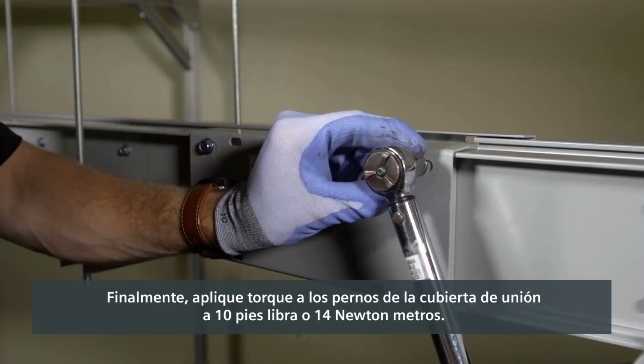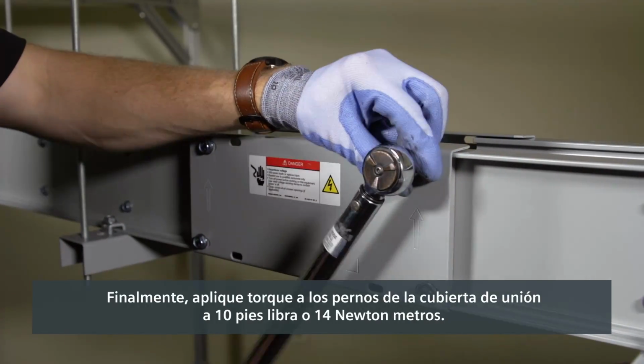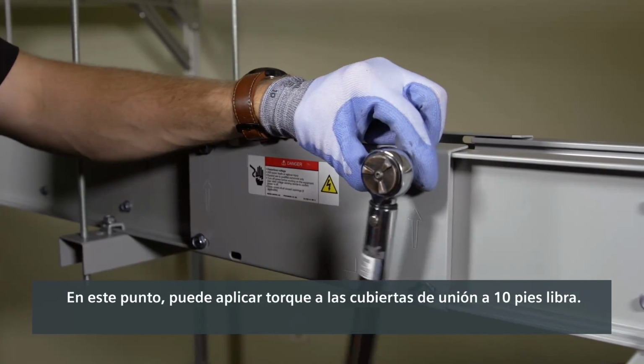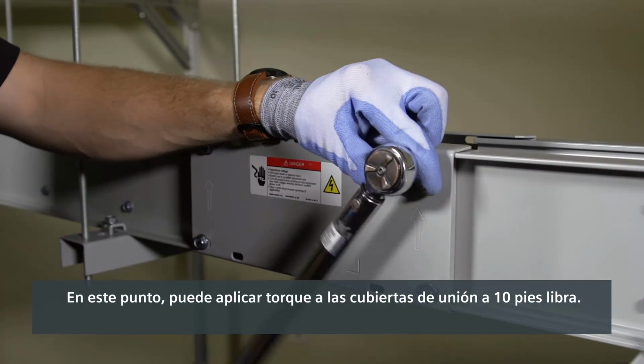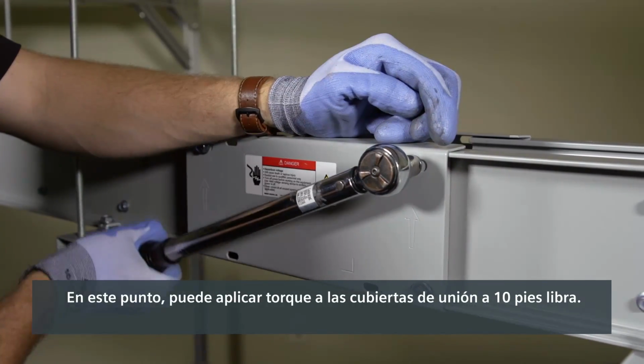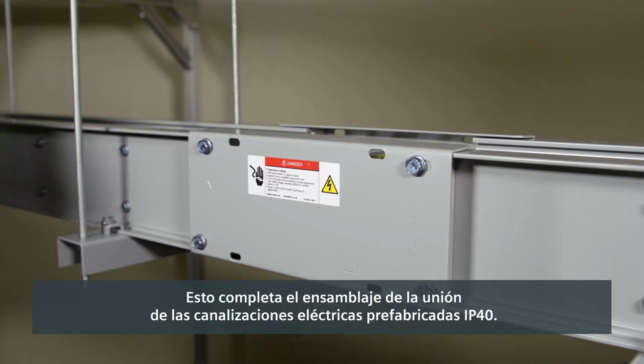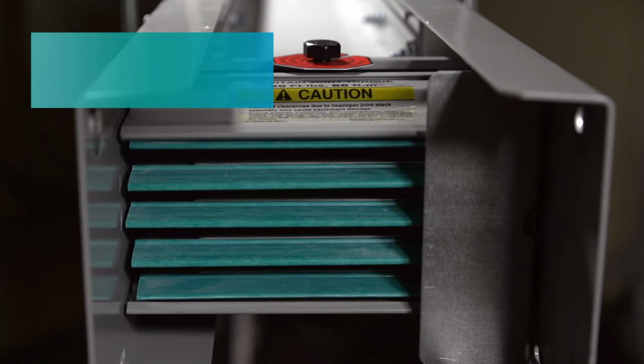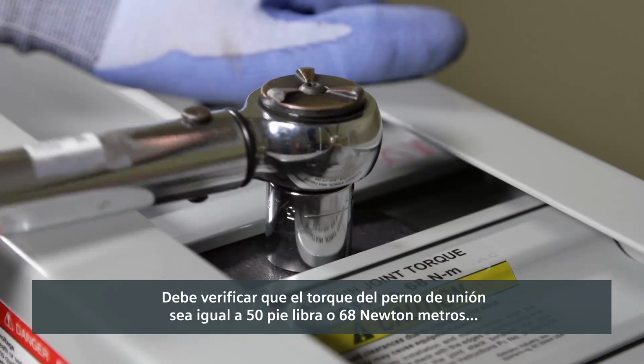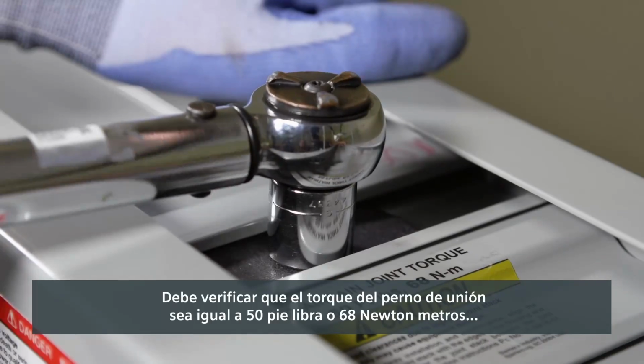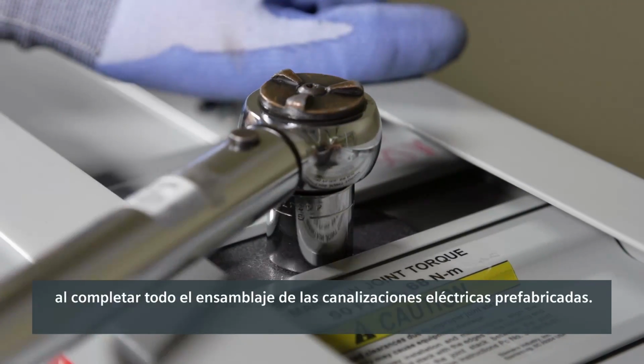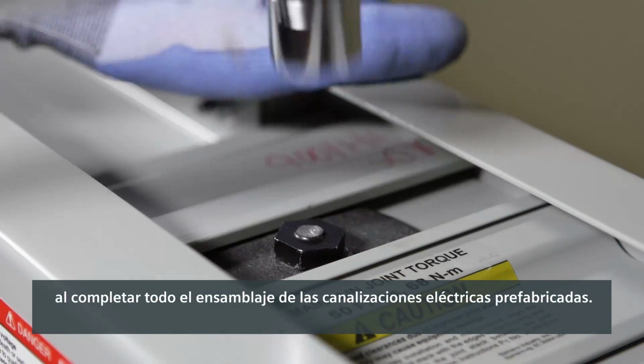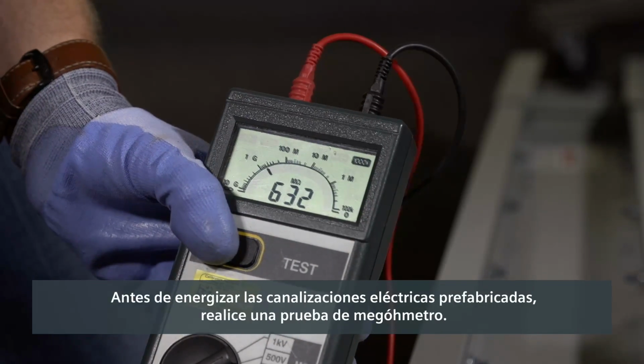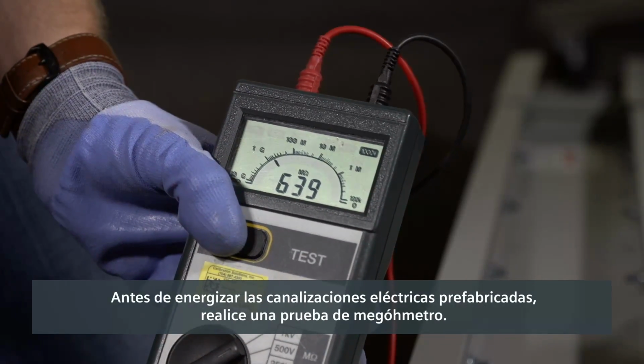Finally, torque the joint cover bolts to 10 foot-pounds, or 14 newton-meters. At this point, you may torque the loose bolts on the joint covers to 10 foot-pounds. This completes the assembly of the IP40 busway joint. Joint bolt torque will need to be verified to be equal to 50 foot-pounds, or 68 newton-meters, upon completion of the entire busway assembly. Before you energize the busway, perform a Megger test.